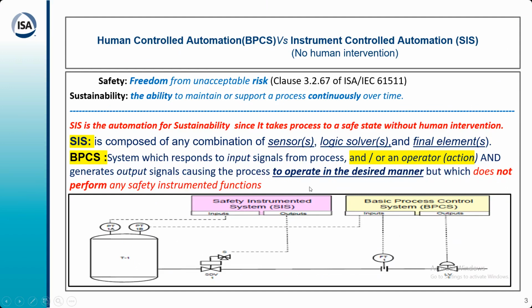And the output of this does not go to an ordinary general purpose solenoid valve. It is a SIL rated solenoid valve. A SIL rated solenoid valve will cost you a fortune. An ordinary solenoid valve may be 4,000, 5,000 rupees. This may be 60, 70,000 rupees. So don't go for SIL 3 for every safety requirement. SIL 3 will cost you heaven, and you cannot afford it. So that is why you have to have a SIS study, SIL study, risk study, and then you can proceed further.